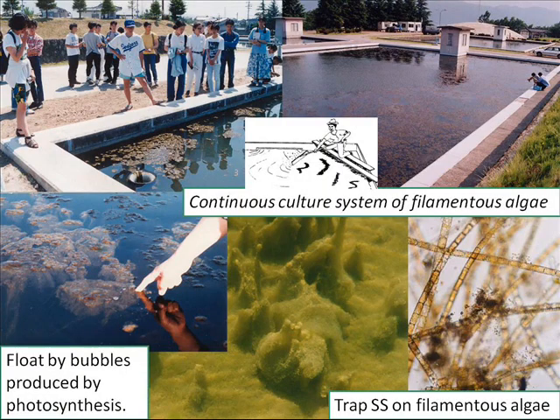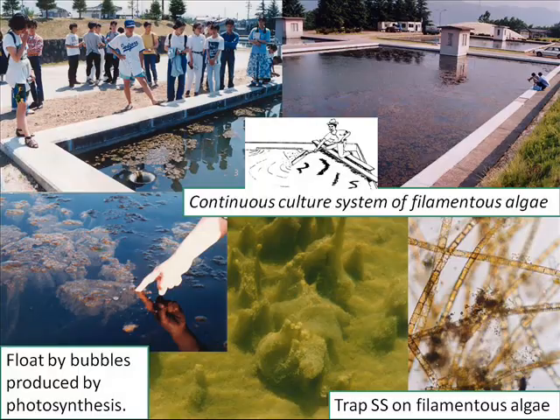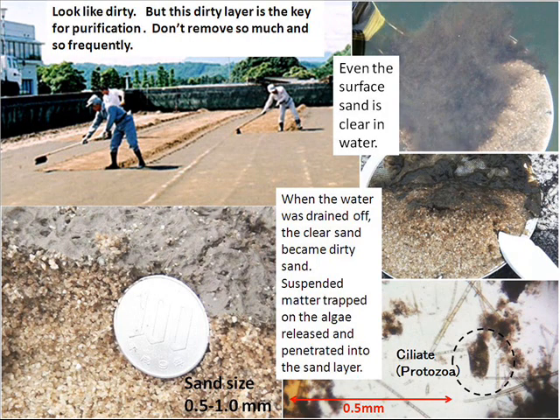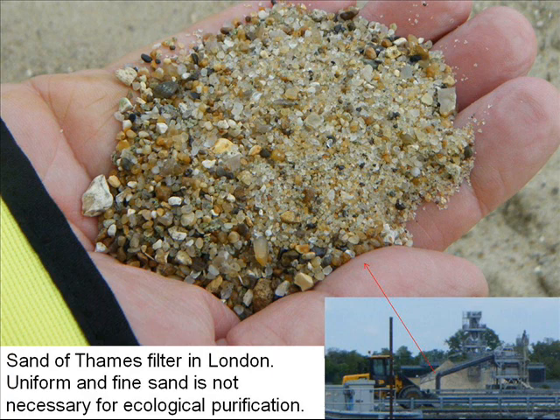A continuous culture system of filamentous algae is the key for the ecological purification system. Algal mud on the bottom lifts up and floats by bubbles produced by photosynthesis. This mud traps suspended matter among the filamentous algae. Floating algal mud runs out automatically from the overflow outlet. The surface mud looks dirty, but this dirty layer is the key for purification — don't remove it too much or too frequently. Uniform and fine sand is not necessary for an ecological purification system — this is the nearest sand media to that of the Thames filter in London.